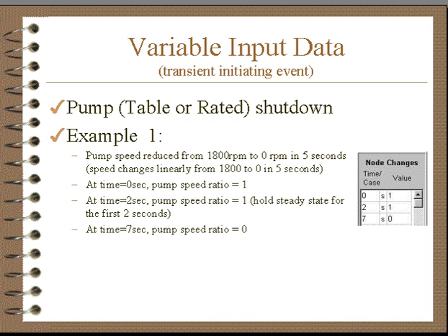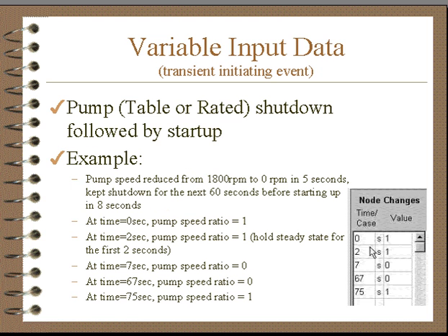When we have pumps described by head flow data, we have to give the speed ratio. We can actually go through one where we can shut the pump down and restart it. This particular one, the pump shuts down from two to seven seconds, and then 60 seconds later it starts up again in an additional eight seconds.